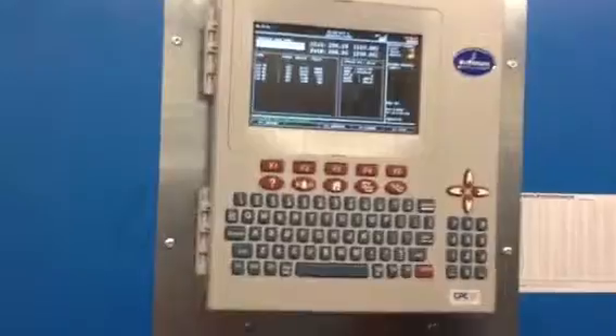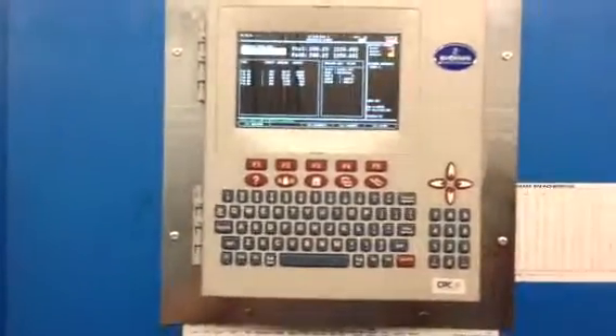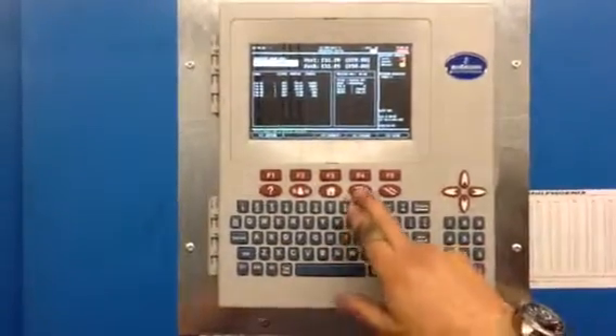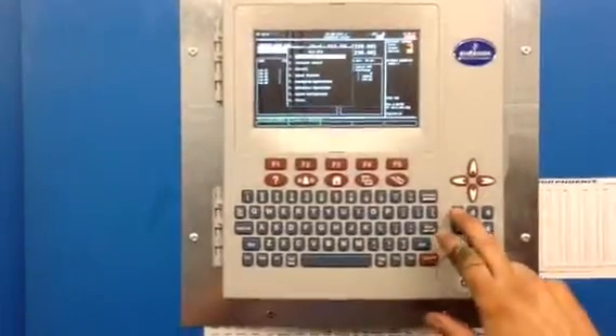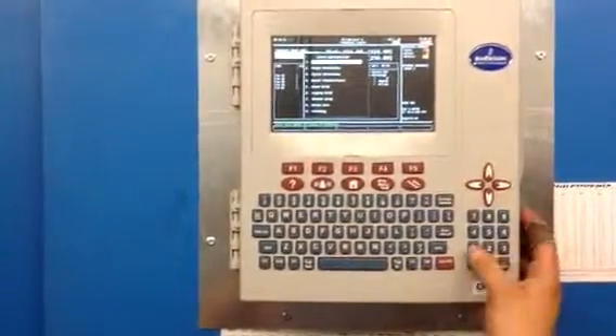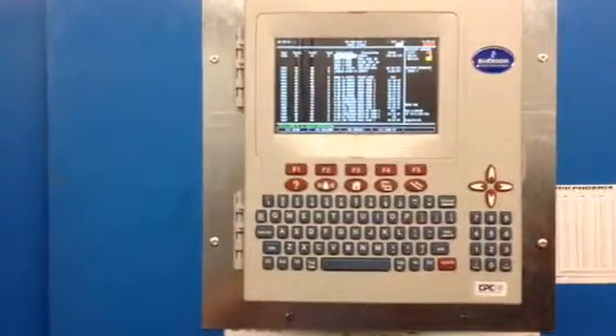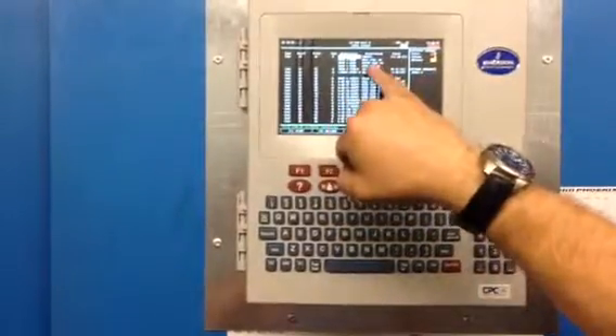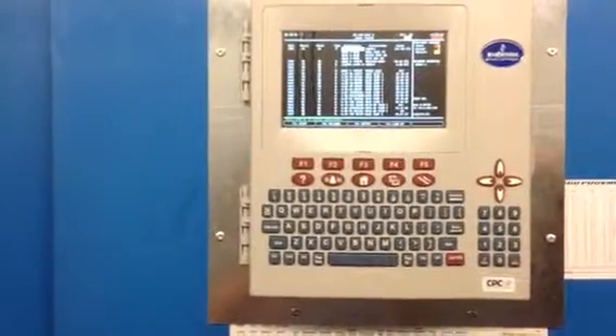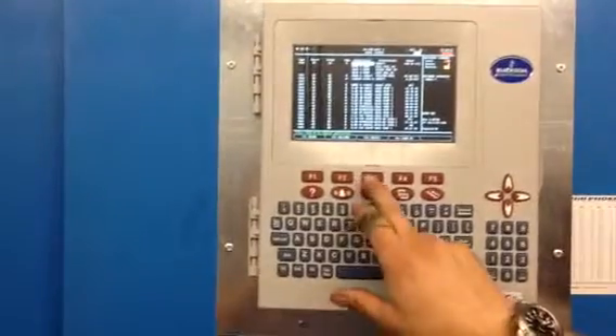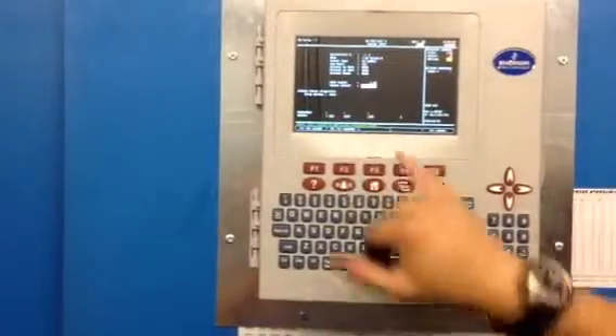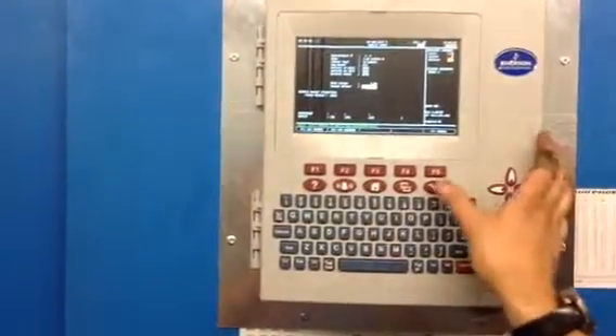208. We're ready, pretty much dead on the money. But if we weren't, we would do the same steps. Menu, 7, input definitions, find rack 4 condenser. Rack 4 condenser, 218 pounds. If we want to offset, we have a 0 offset.